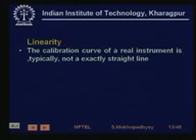So then the next point is linearity. Although instrument calibrations will not strictly follow a linear curve, it is still very useful to imagine the system as a linear one, so that you can very easily interpret the true value. If you have an instrument sensitivity of, let us say, 10 millivolts per degree centigrade, then if it gives a 25 millivolt signal, you know that the temperature is 2.5 degrees centigrade. So you can get it just by dividing by a number or sometimes adding another number to it.